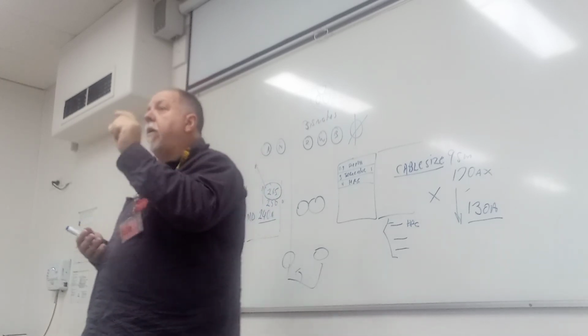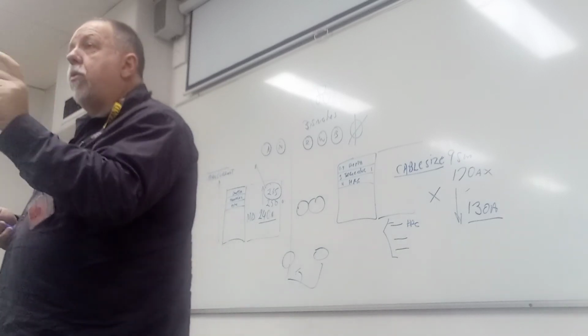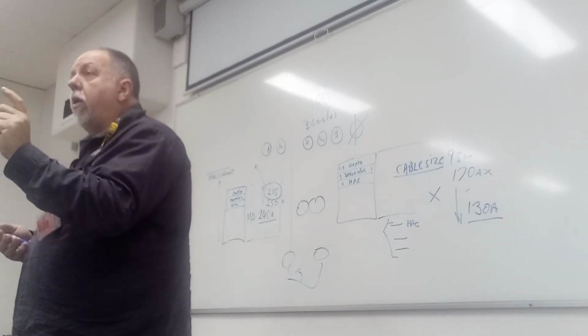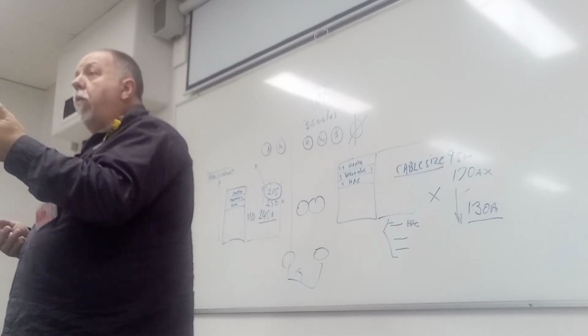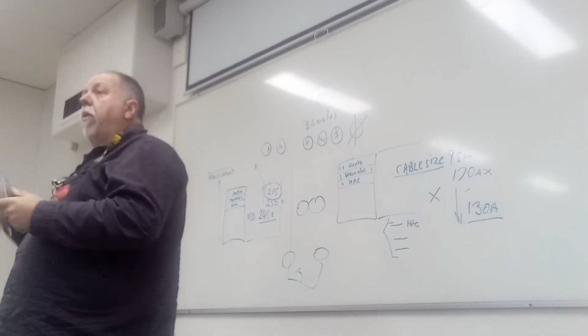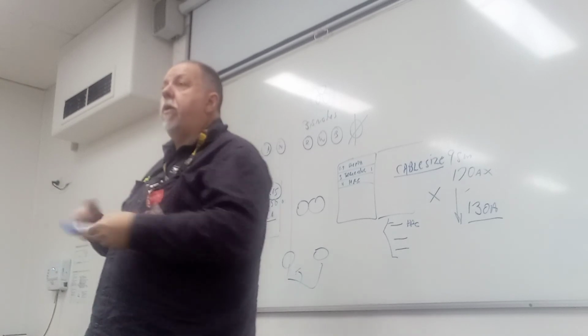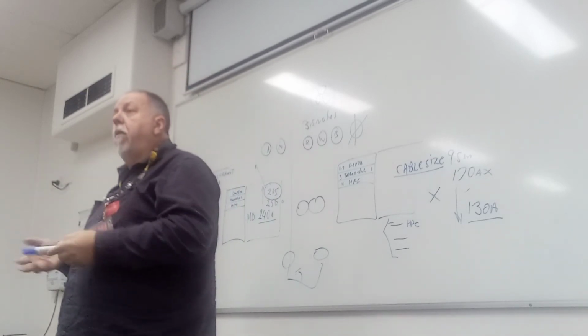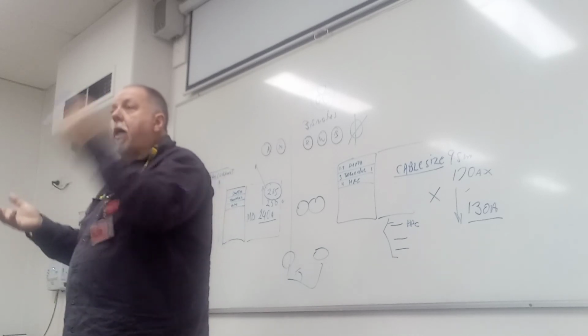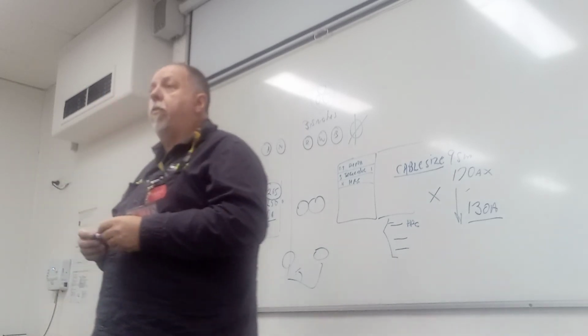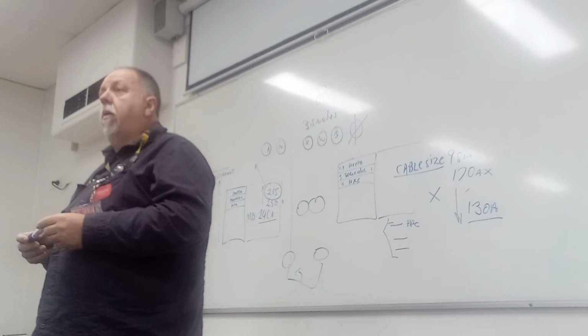Exactly, you don't divide the 200 amps by the 2 cables, or the 400 amps, whatever it was. They don't divide it by the number of cables. So they apply the full load maximum demand. It's like they were looking for the full 400 amps, whatever it is, to look for that type size, and then divide and build it all up, and then not really thinking, well, I had to cut that in half because I got half the current going through each cable.